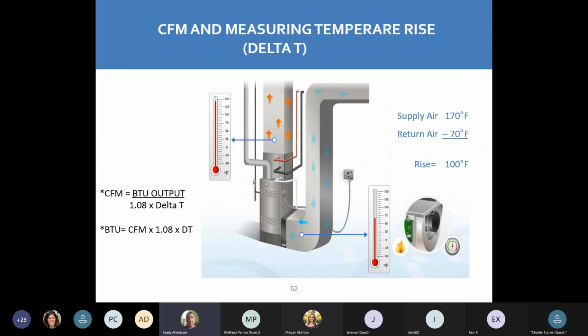Heating season was horrible for pleated filters. High limits, day in, day out. Changing temperature rises 15 to 30 degrees on a brand new 3M filter out of the package. So be mindful when your air conditioning comes up, what kind of filter they have in there. Get a box of 12 of disposable filters, not the pleated ones, just the cheapies. Carry them in the truck. Trust me, you're going to use them.